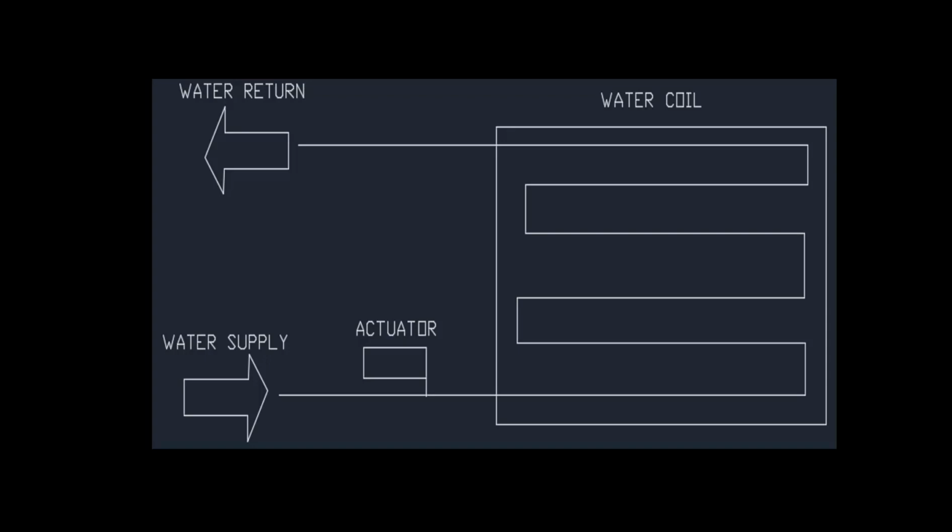Titus gets asked, how low can the GPM be? The answer is, it depends. We have to find a happy medium between laminar and turbulent flow in order to effectively heat our space temperature. With a GPM too low, the water will enter the laminar state, which is inefficient for heat transfer. With a GPM too high, the building hot water system becomes very energy inefficient.